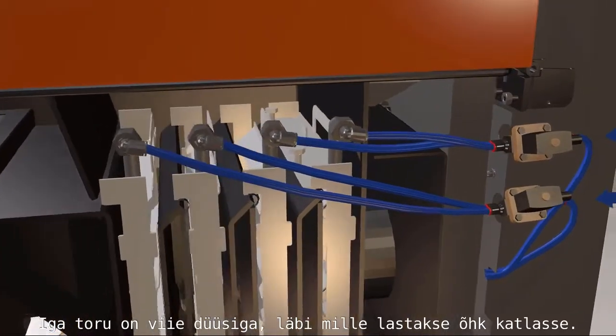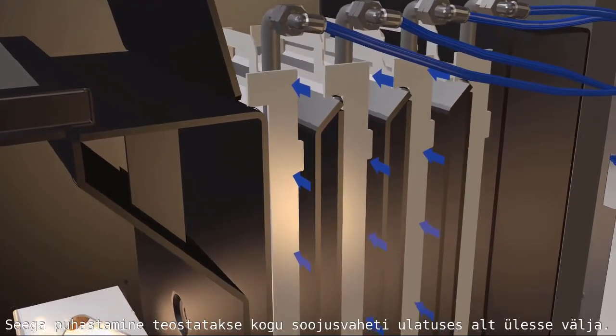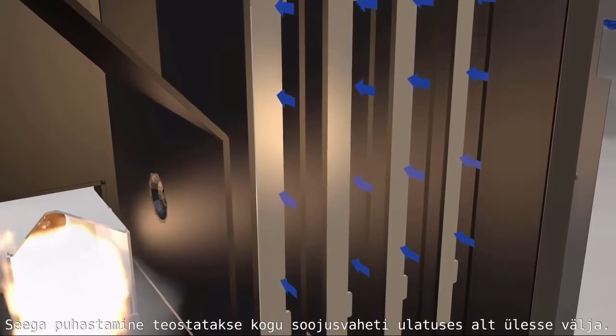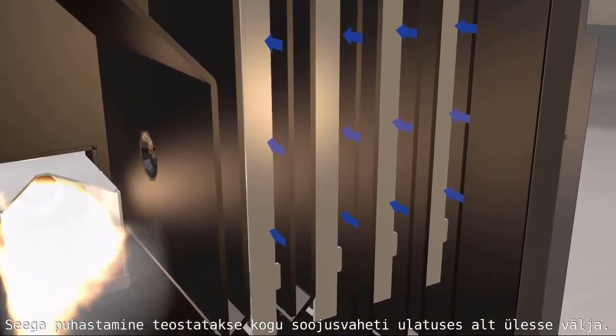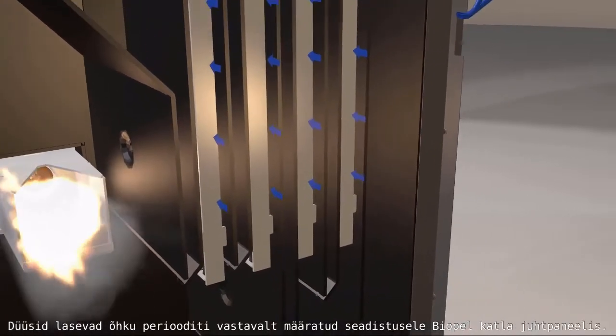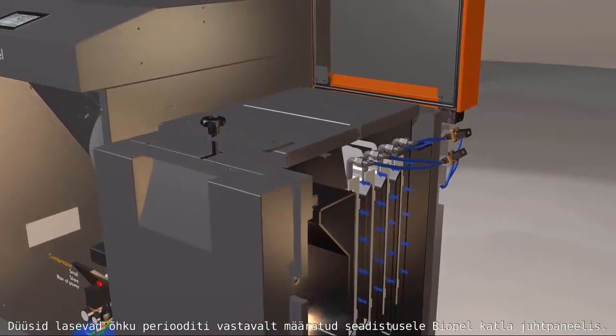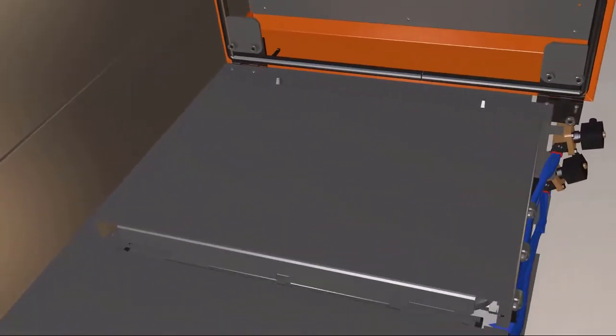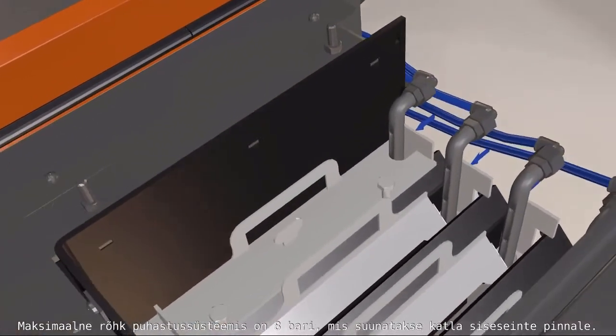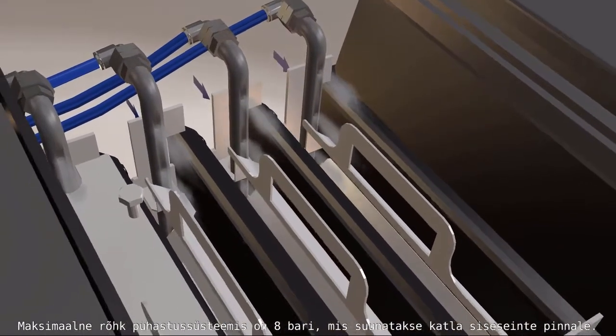Each air pipe is provided with five nozzles which release the air inside the boiler. The cleaning is performed throughout the wall heat exchanger from top to bottom by a total of 20 nozzles. These nozzles release air periodically and are opened and closed by the setup of Biopel's control unit, providing a maximum cleaning pressure of 8 bars directly at the boiler surface from the closest distance possible.